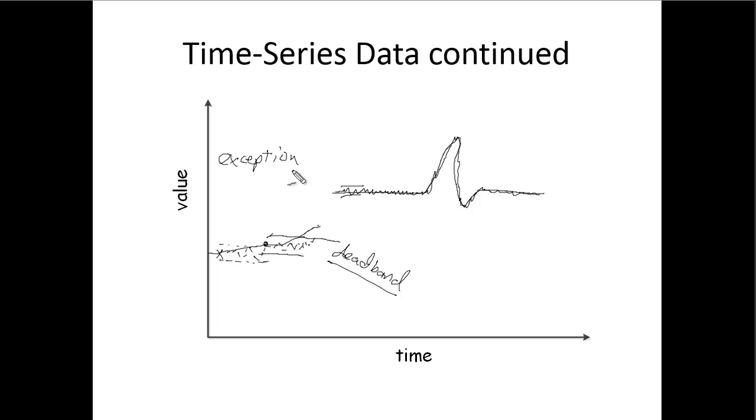Okay, and that's my exception, my deviation and my exception. So I say if it's inside this deadband, just filter it out. I don't need to see it. There's no reason for me to have all these little readings in my database taking up a bunch of space when it's just noise. Okay.